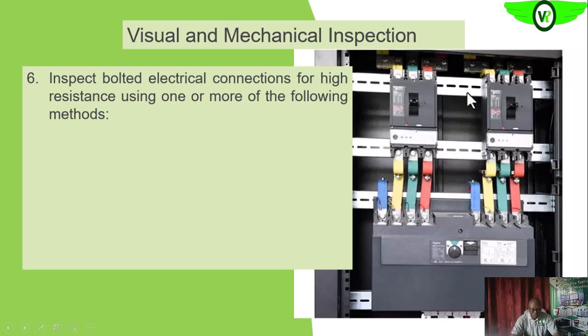Okay, so as you can see, you can use this table to determine the normal torque value for all of these bolted connections. You also want to check to see that there are no signs of high resistance. Signs of high resistance will show up as metal oxide deposits, those greenish or whitish substances on these joints. Those deposits are clear signs of high resistance, and those can cause hot spots on the circuitry, which we do not want. Okay, so we can use a low resistance ohm meter to determine whether we have a high resistance joint. After cleaning, we can place one probe of the low resistance meter here and the other one on the bolt to see that the bolt and the bar are making proper connection, that the resistance is as close to zero as possible, zero preferably. So that is what we want to do on all of these bolted connections to see that no resistance is building up.